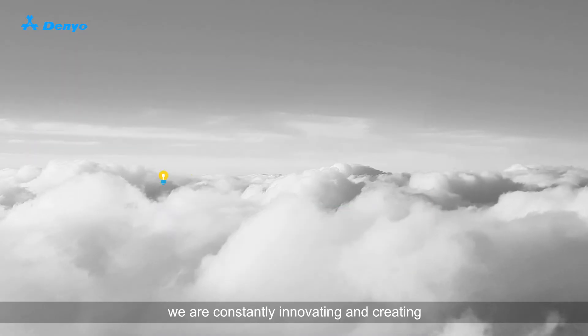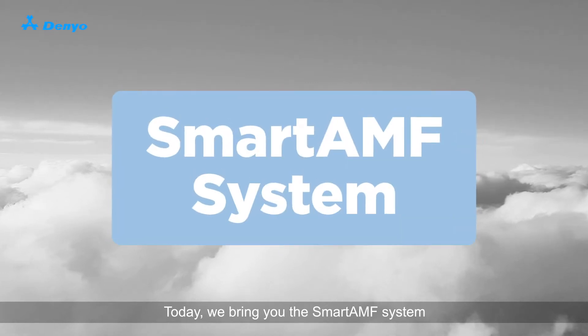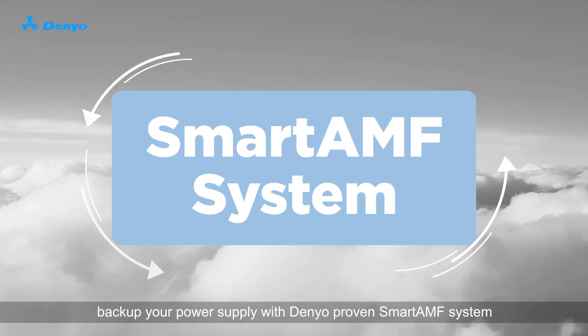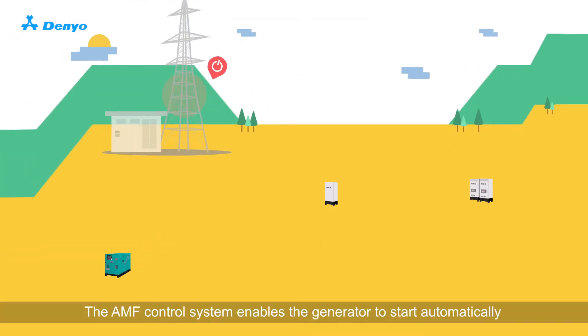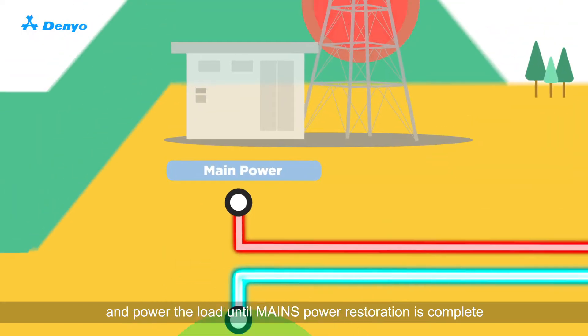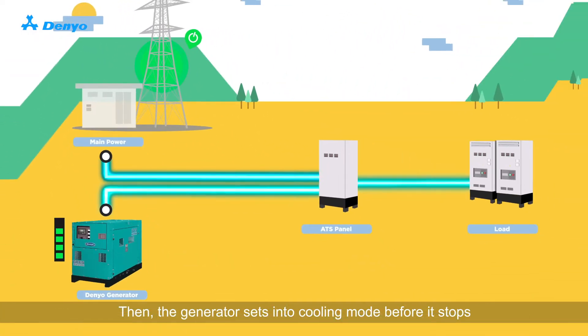At Denyo, we are constantly innovating and creating. Today, we bring you the Smart AMF system. Back up your power supply with Denyo's proven Smart AMF system. Experiencing mains failure? The AMF control system enables the generator to start automatically and power the load until mains power restoration is complete. Then, the generator sets into cooling mode before it stops.